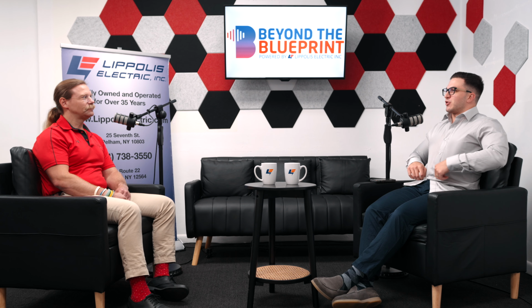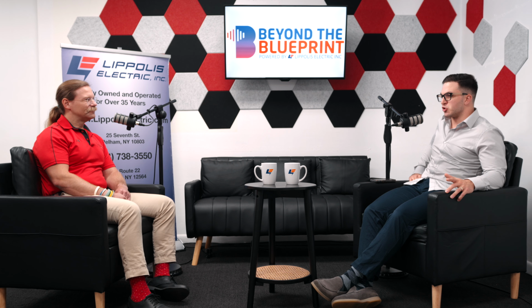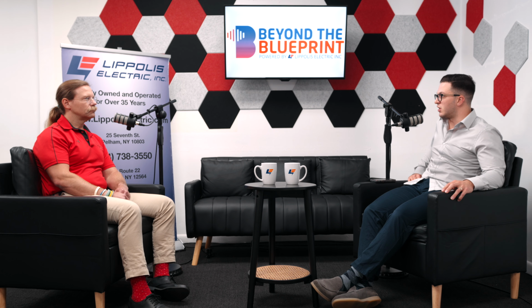So Patrick, aside from your really cool mustache, I think we have a lot of great things to talk about today, specifically for professionals in the engineering field, facilities management, industrial data centers, hospitals — the do's, don'ts, and horror stories of our experience in the industry, and what happens when you don't do certain things that are outlined in books such as NFPA 70E, IEEE, NFPA 70B, the NETA standard. With your experience in the industry and all the different types of facility safety and damage mitigation services we provide, I think the crux of it all is arc flash hazard analysis. I think when a facility has a proper arc flash, short circuit, and coordination study in play, you can go down the line of the preventative maintenance measures to follow to mitigate electrical fire hazard and building interruption.